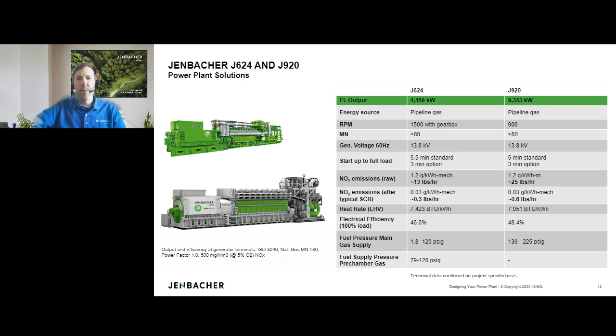Start times anywhere between 3 and 5 minutes are the standard. NOx emissions are around 1.2 grams per mechanical kilowatt hour, or 13 pounds per hour. But obviously we know that in many cases SCRs are needed, and that can be dropped down very substantially. We have SCR catalysts with 95 to 97% reductions available, which will then drop those NOx emissions substantially. The heat rate is about 7,400 based on LHV, so obviously an excellent heat rate for this product. And this is a high-speed engine, at 1500 RPM with the gearbox design.